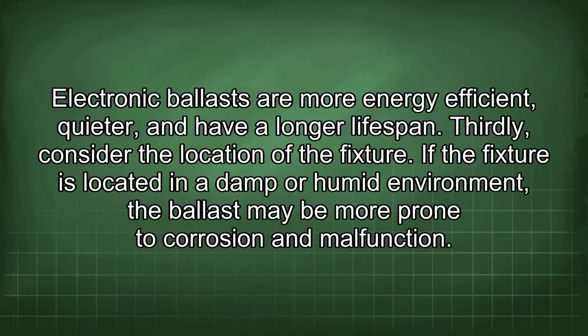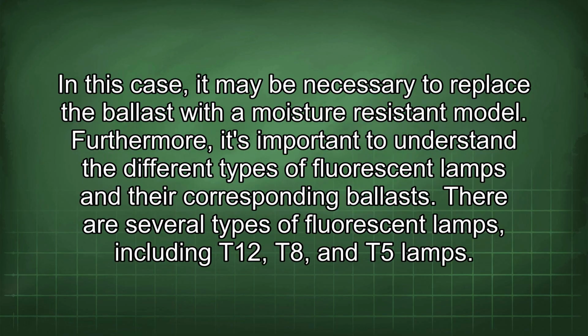If the fixture is located in a damp or humid environment, the ballast may be more prone to corrosion and malfunction. In this case, it may be necessary to replace the ballast with a moisture-resistant model.